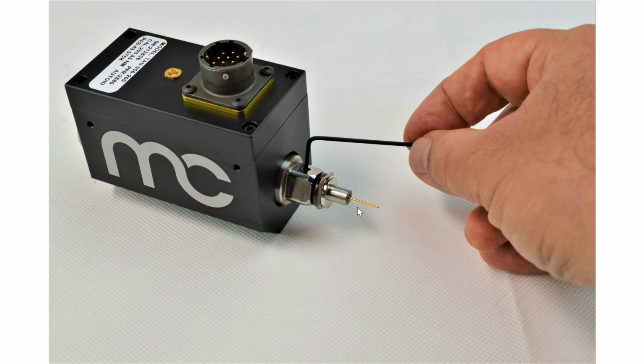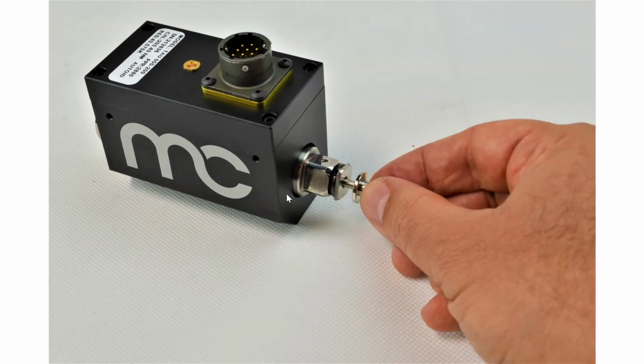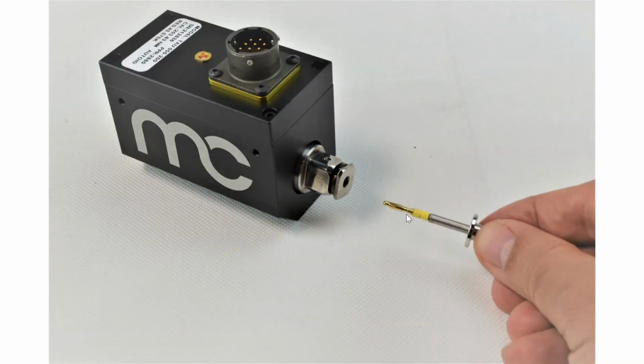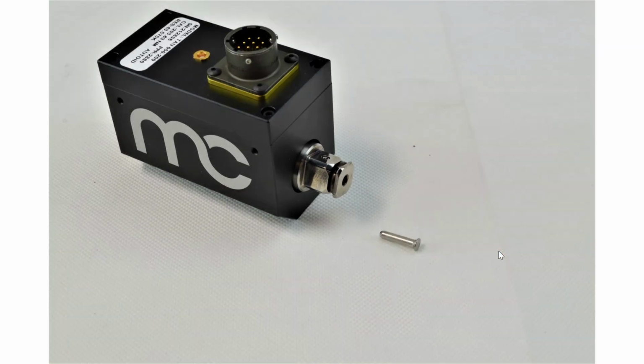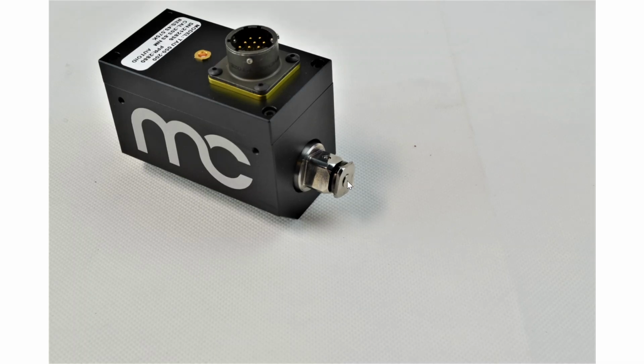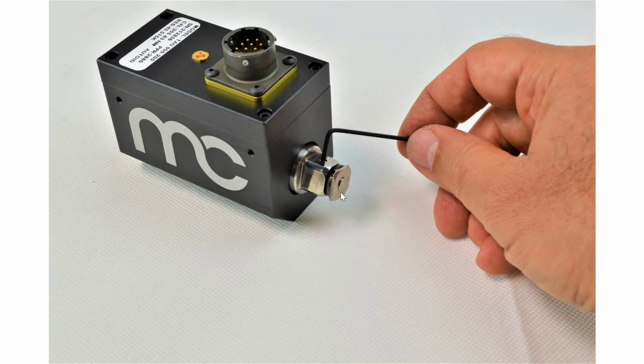The other feature is to take out the whole ultrasonic section and make the whole system, the TAW transducer, just a torque and angle unit. Sometimes you don't need the ultrasonic, so you can just use the torque and angle. This would protect the ultrasonic section, and then the transducer would act like a torque angle unit. So here, by loosening this set screw, you can pull out this section. So everything is out. Now you can use the filler, insert in this area and push it in. Then use the wrench to tighten this filler that's in there. This will make sure there is no debris that will get in there.